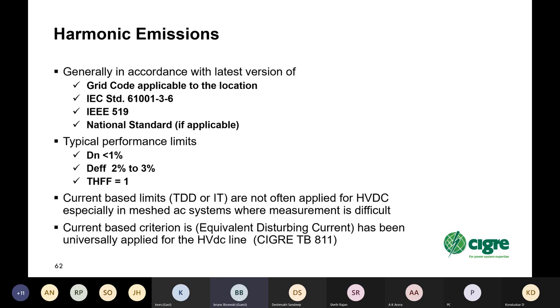Harmonic emissions should generally be in accordance with the latest version of the grid code applicable to the location, or IEC standard 61000-3-6, IEEE 519 in North America, or a national standard if applicable. Typical performance limits for distortion: less than 1% for individual harmonics; total harmonic distortion, or effective distortion of all harmonics, 2% to 3%; and telephone harmonic form factor, typically 1%. Those are typical for HVDC systems.